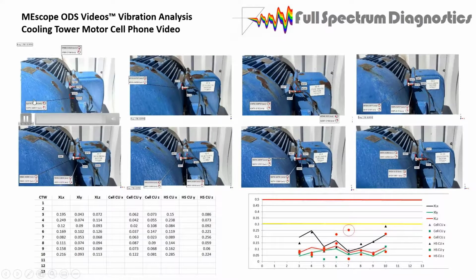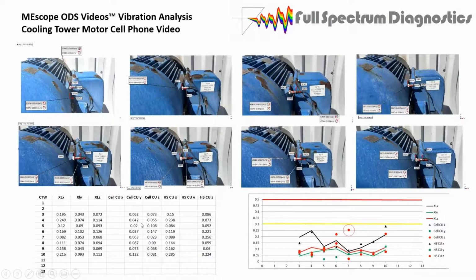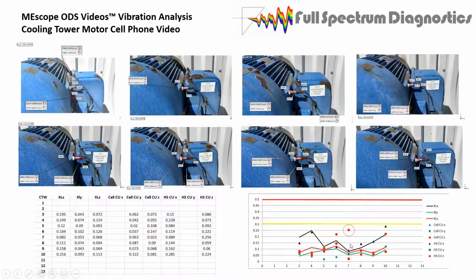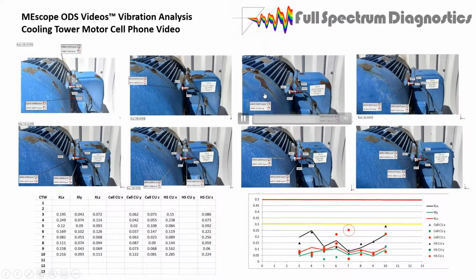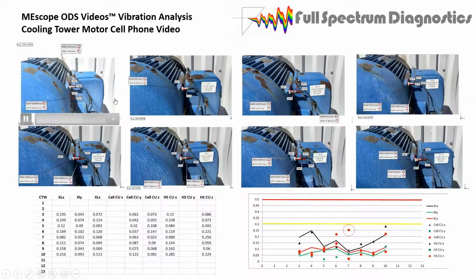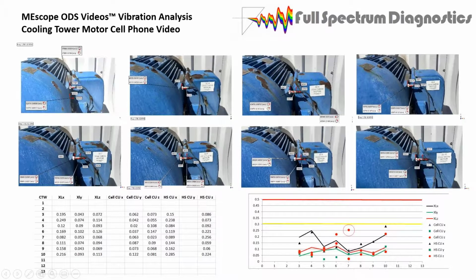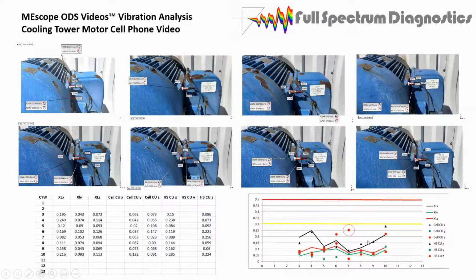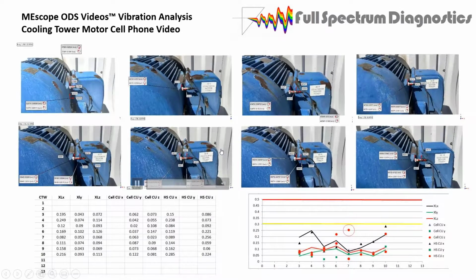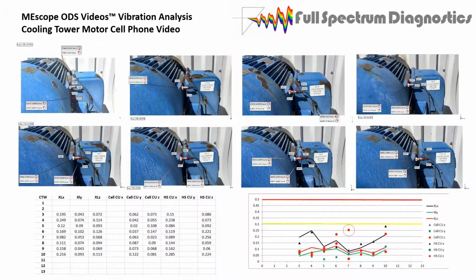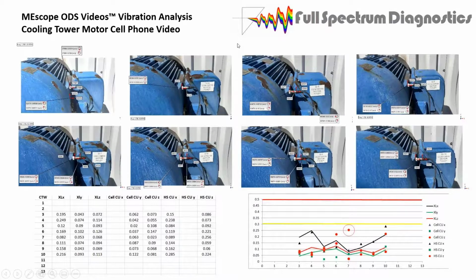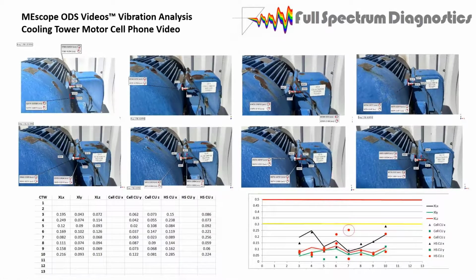What we're looking for now, once we say, yeah, this is a pretty good estimate of the alarm levels, and we're probably okay, the video is doing a good job. Now we look at the motion and try to see what we can see. And if we can trust the amplitude level from a close-up, any other direction should work out the same way. And now we can see the entire structure. As long as we scale it properly, we can judge the amount of defect in it.